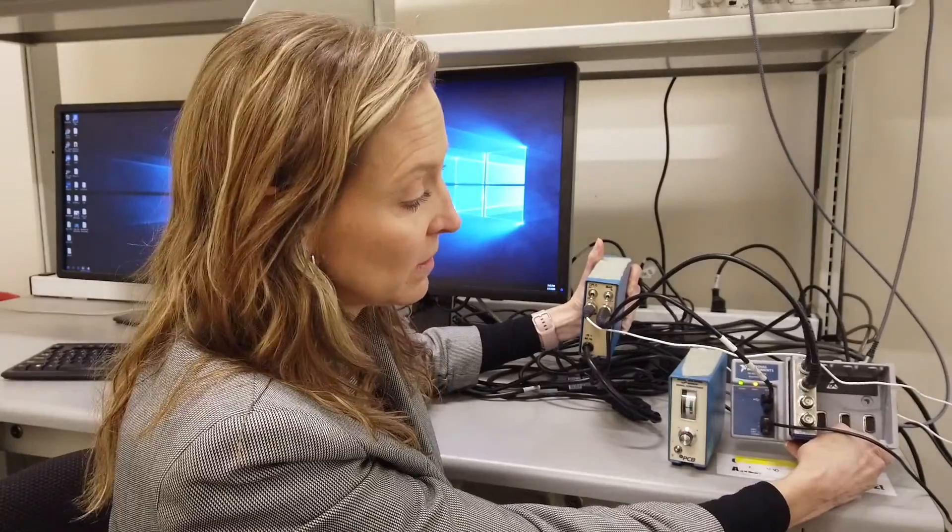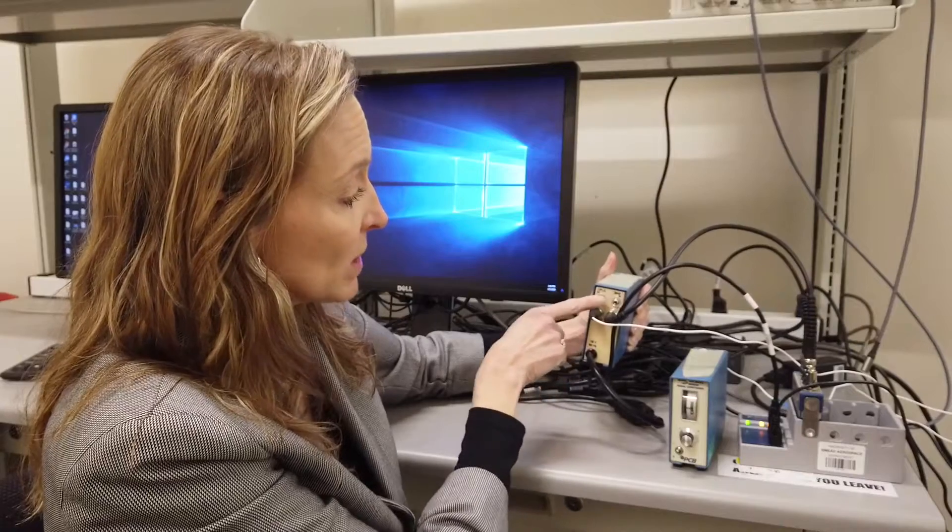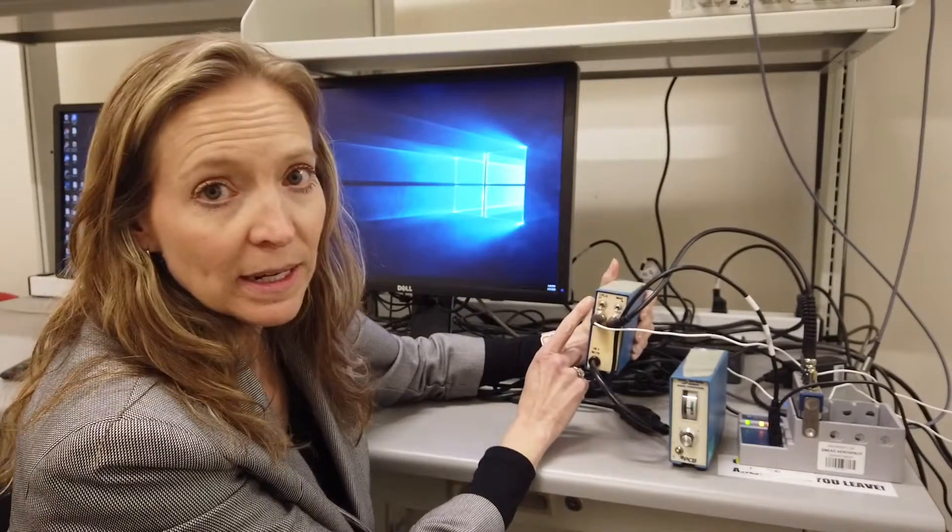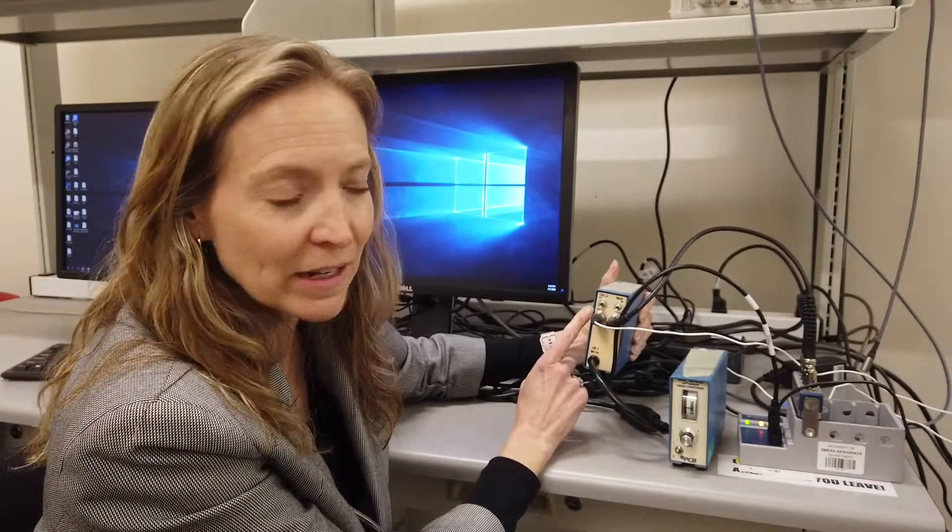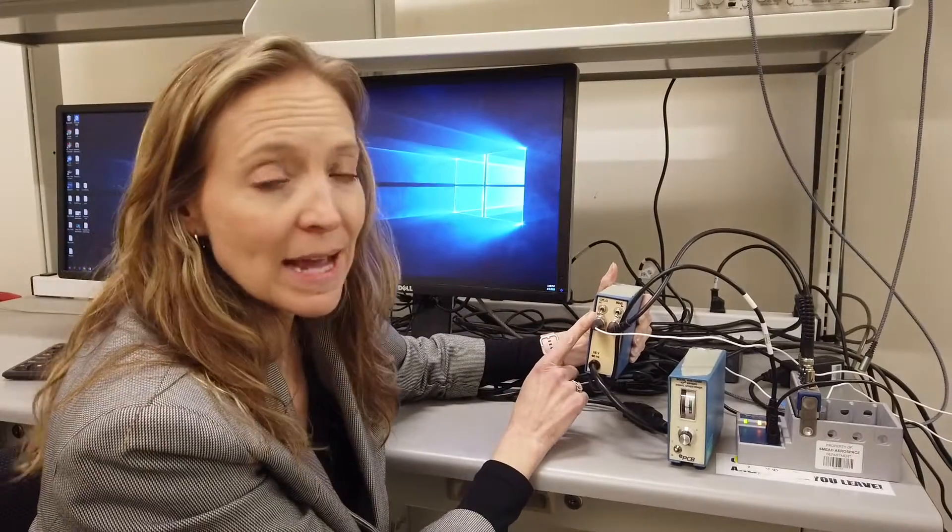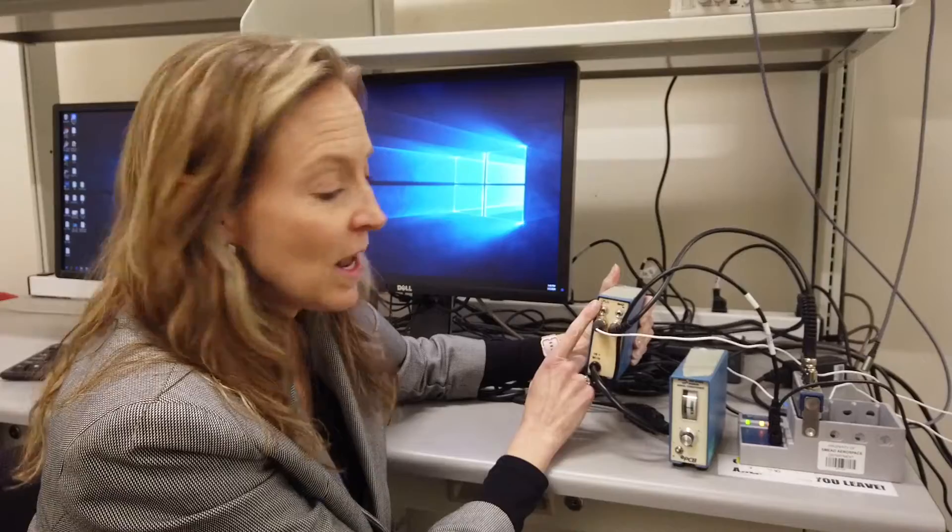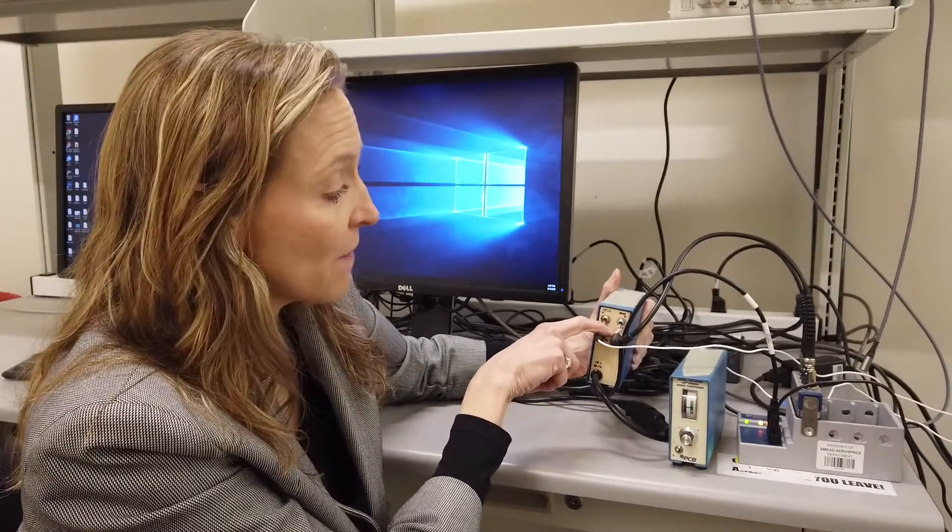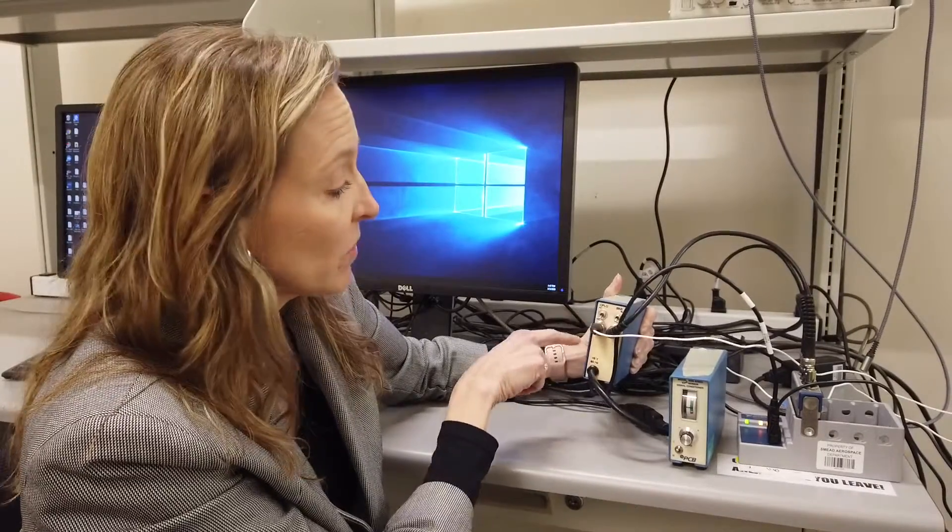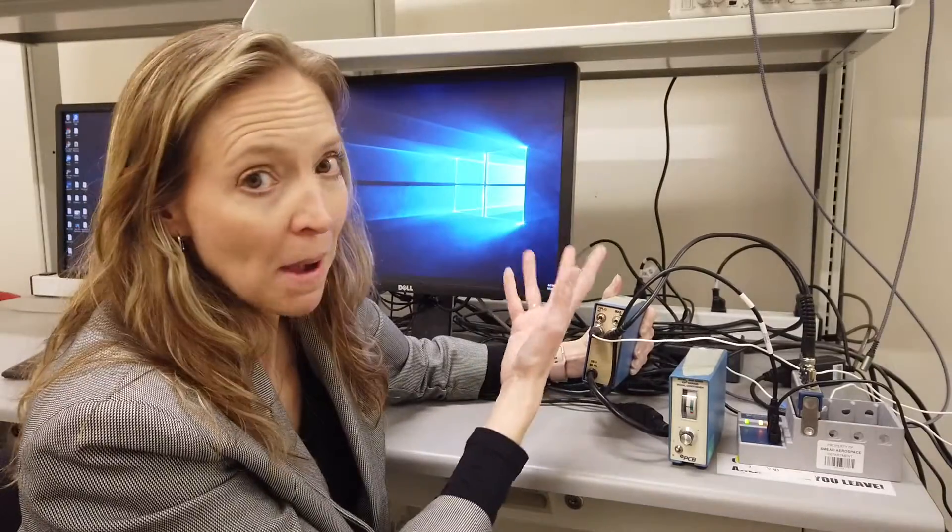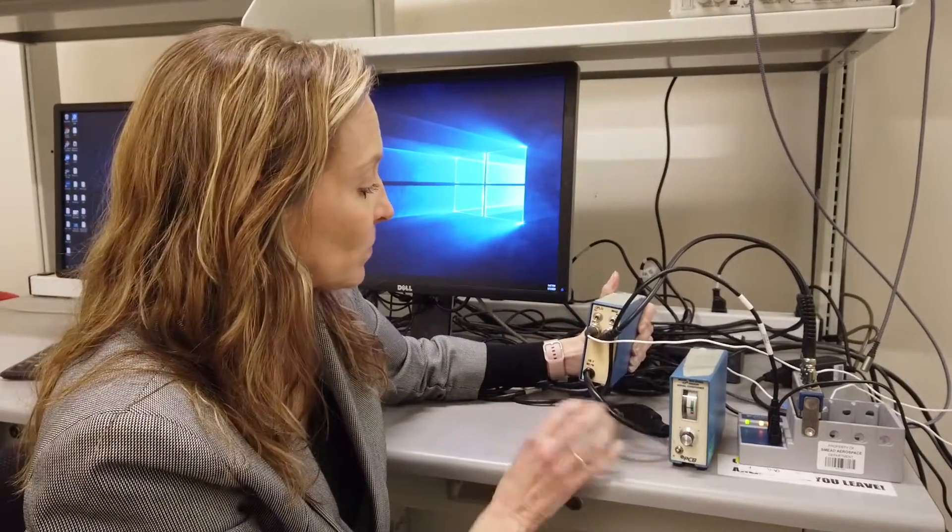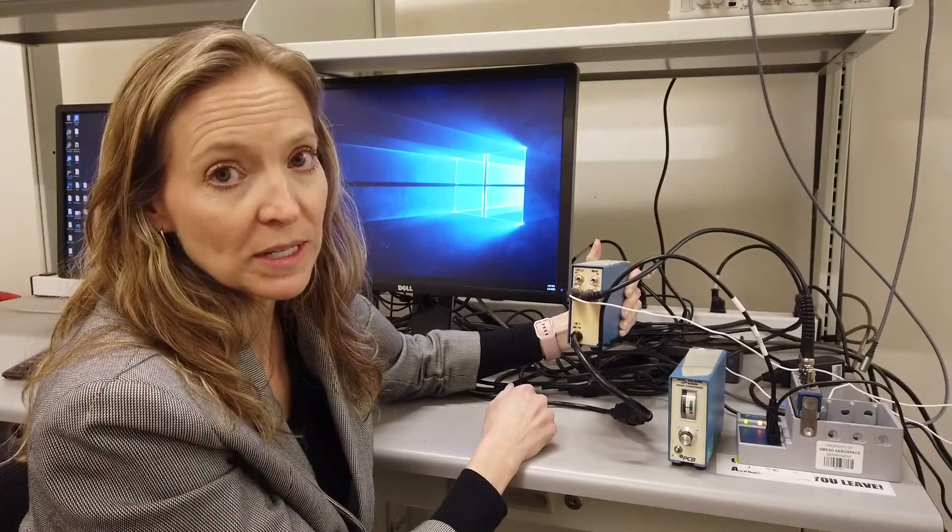There are some important settings here for the coupling, AC or DC coupling. Again, you'll learn about that more in the electronics class. Very important that this needs to be set at DC coupling instead of AC coupling. We also want to have our bias voltage that's provided to the sensor at 11 volts, not 6 volts. So both of these switches should be in the down position. Sometimes they get bumped easily, so double-check that.